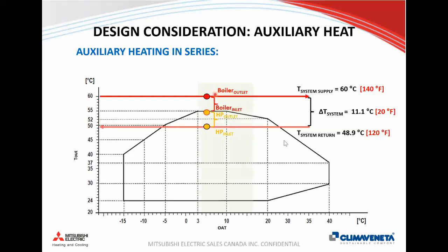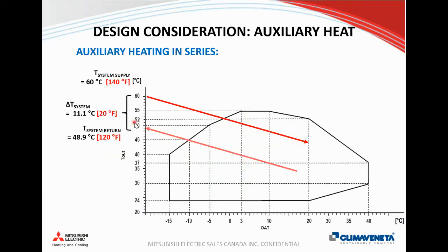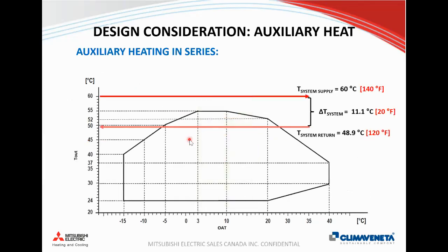So if you did want to say, okay, well, let's do series heating. Let's have the heat pump bump it up by 5 degrees and then have the boiler bump it up the other 5 degrees. That's fine whenever it's between 3 and 10. But what happens later tonight whenever it's minus 10? If your return temperature is 50 degrees or higher, maybe it's here, the heat pump's going to say, well, you're telling me to make 45-degree water, but it's 52 degrees. I've done my job, and the heat pump will actually never run. In reality, your boiler's on a reset curve, something like this, so it'll work down to the lower end. So it's important to design your systems to have the lowest return temperature possible to get the heat pump to run more. And if you have any questions, feel free to reach out to me.